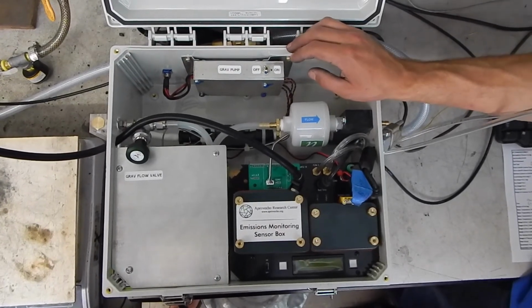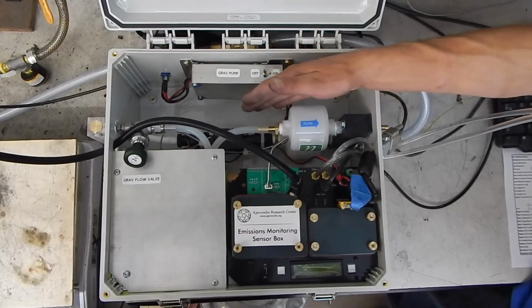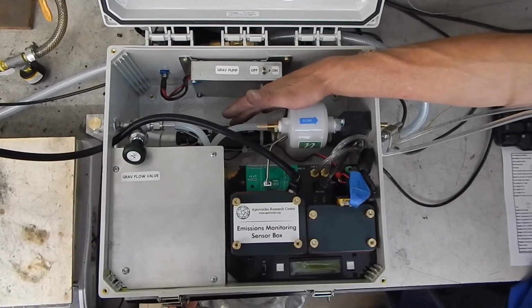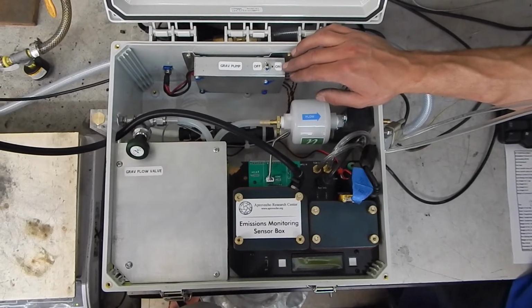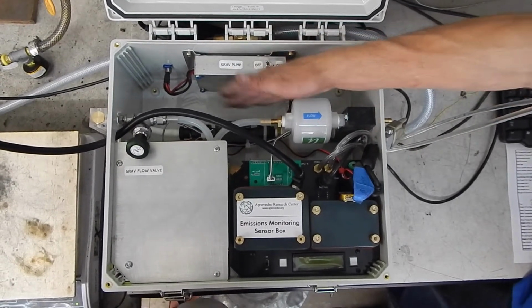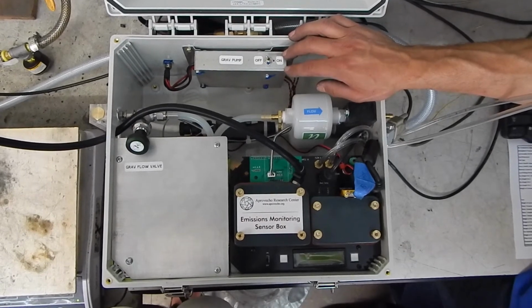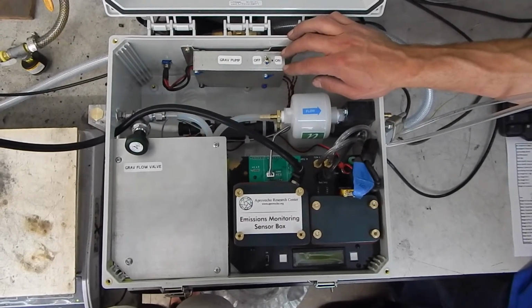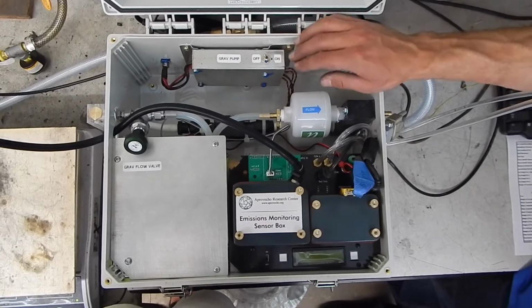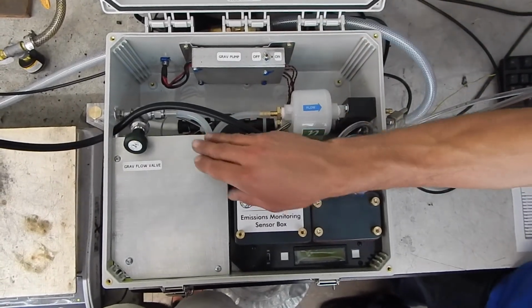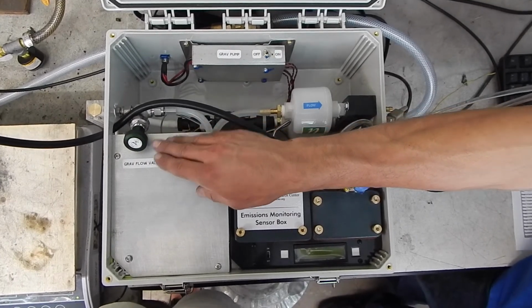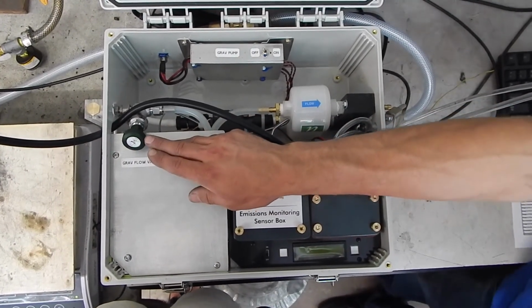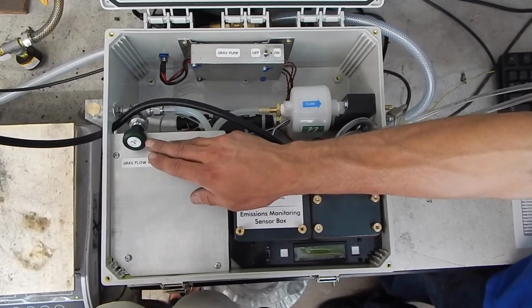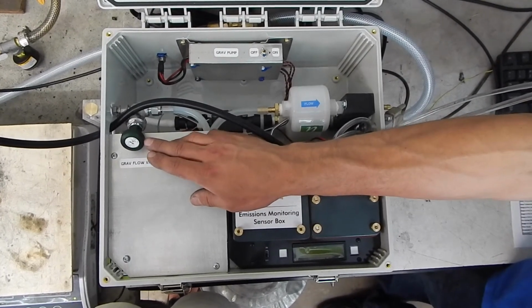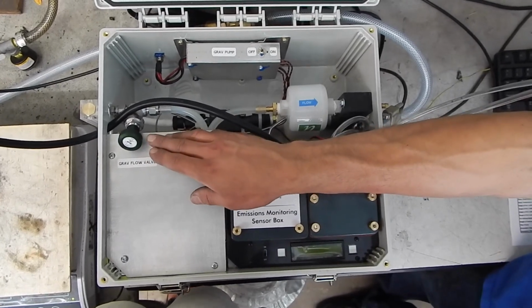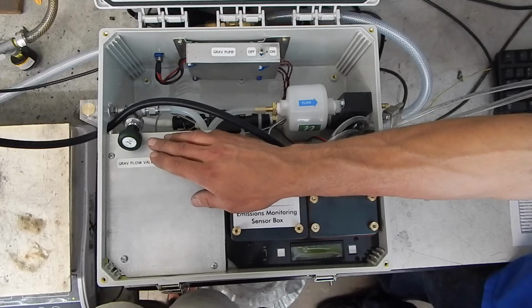We're looking inside the system now, and here's the sensor that's used to measure the flow rate through the gravimetric system. There's space for another unit so that during LEMS measurements, when two filters are used, we can measure the flow rate of both. This system doesn't use a critical orifice to control the flow rate. It uses a needle valve. So that's something that's not optimized for laboratory use. It's optimized for portable use. This valve doesn't take as large of a pump to operate, but it requires more frequent calibration.